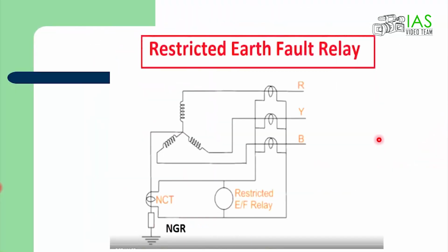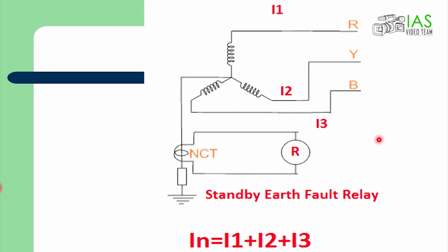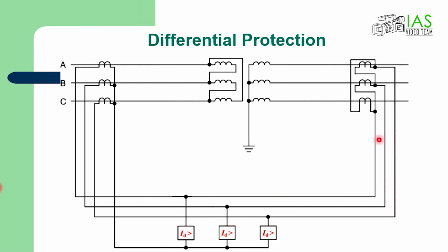Restricted earth fault, again another picture, phase transformers and neutral transformer, and standby earth fault. Standby earth fault detects only the transformer neutral earth. It detects only that, and you can set the values according to what you want. So, generally this says In equals I1 to I3. When this is balanced, In is 0. That is your basics. So, differential protection is something like that.